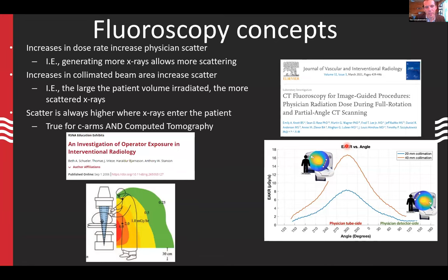There's a lot of misconceptions in CT fluoroscopy in general—a lot of physicians think they'll get way more X-ray dose from a CT scanner than if they were doing an interventional procedure on a C-arm. But all the same fundamental things we know from C-arm fluoroscopy apply in the CT suite: if we have a bigger dose rate, the physician scatter is going to go up.